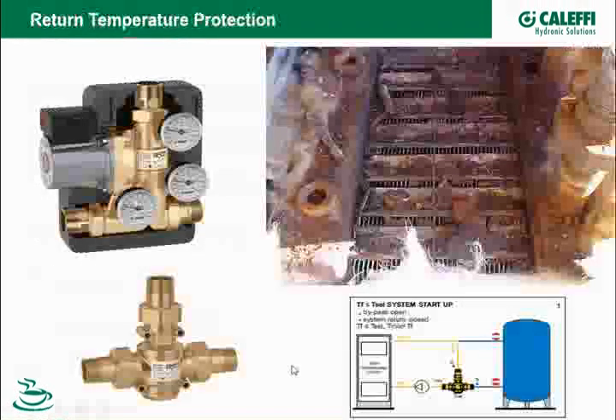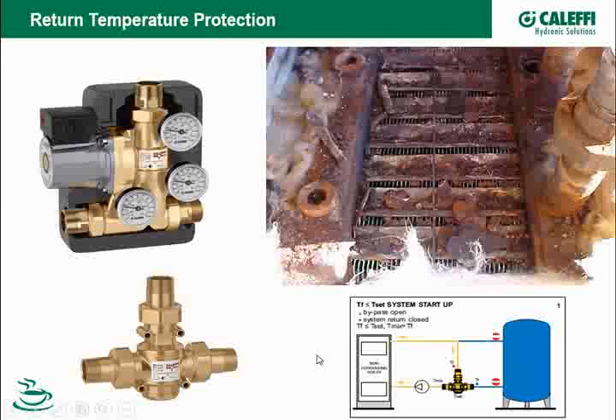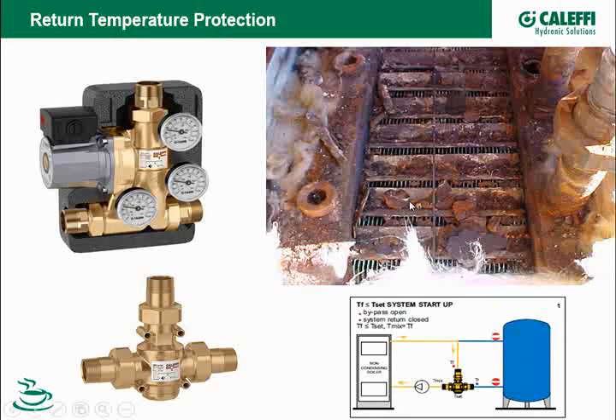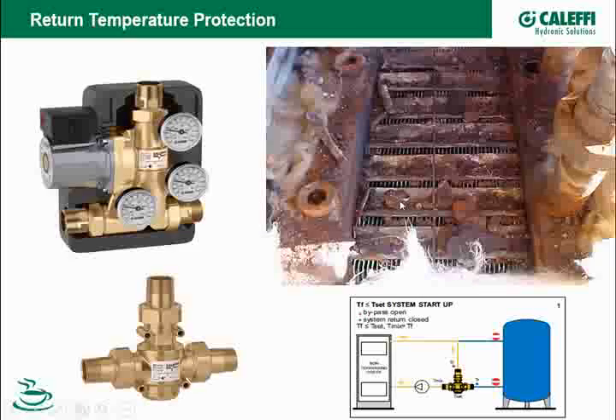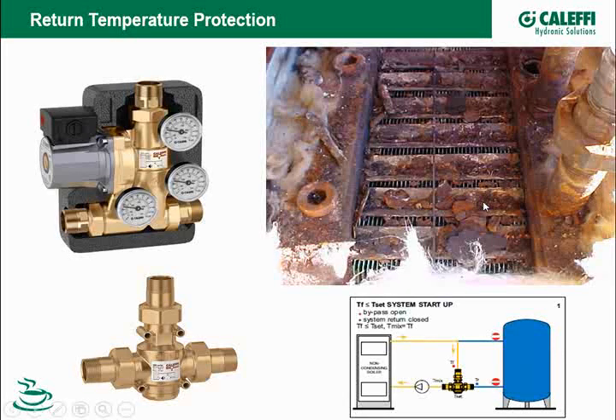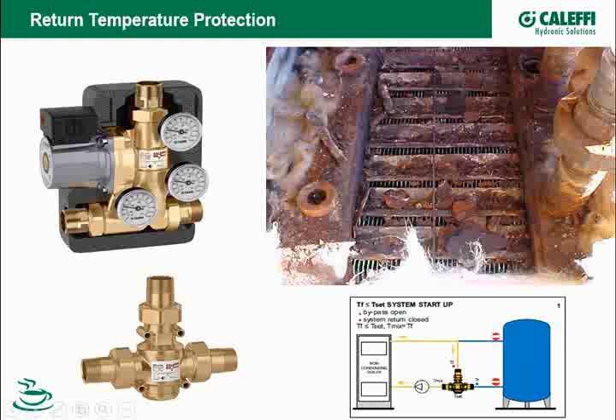Another issue that often gets overlooked is return temperature protection on boilers. Here's an example of a copper tube boiler that's been corroded pretty badly. You can see some of these big particles that have dropped down, or some of the B vent that's corroded, because this boiler's been running in a condensing mode for extended periods of time. Years ago when these boilers came out, we were told that they could handle low return temperatures for periods of time. That didn't exactly prove to be true.